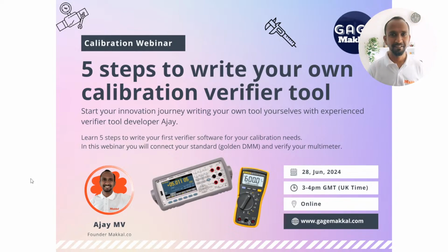So we will look at the 5 steps to write your own calibration verifier. In many cases when we start the calibration, before we even do the calibration, what we need to do is something called verification. So we need a verification tool that lets us verify whether the instrument is ready for calibration, needs a calibration, or we are okay with the current tolerance levels.